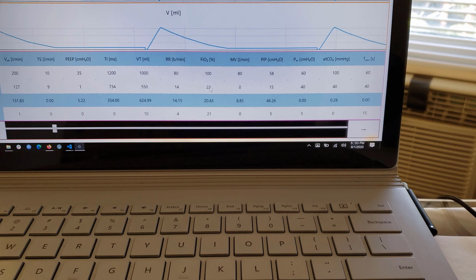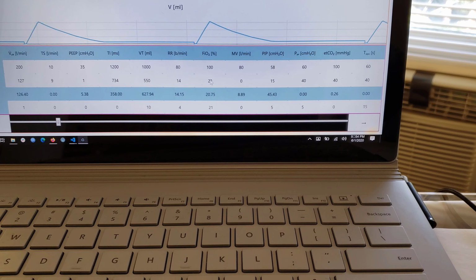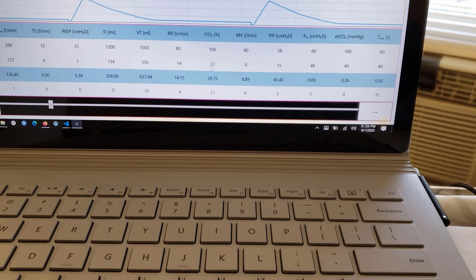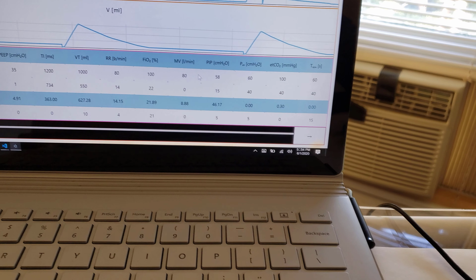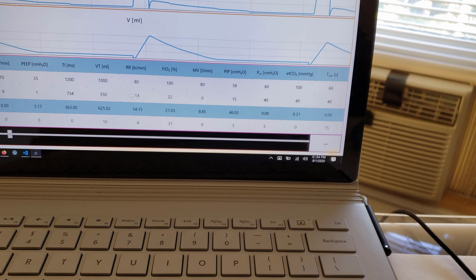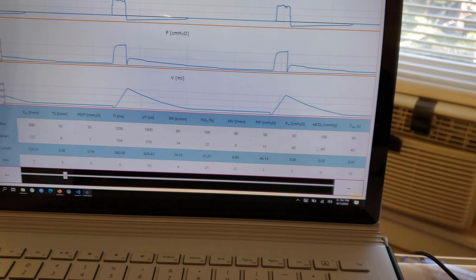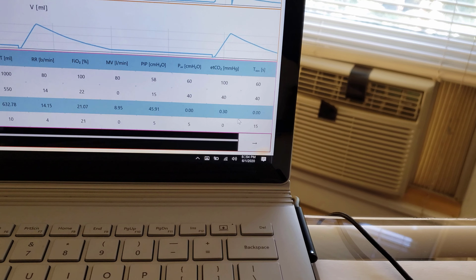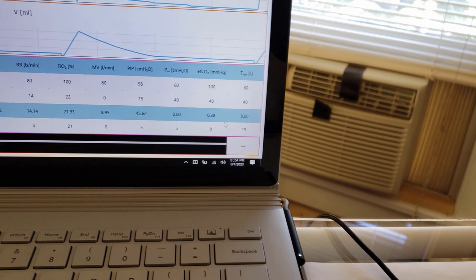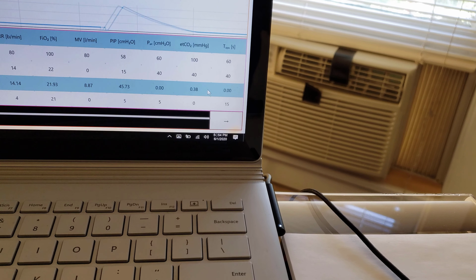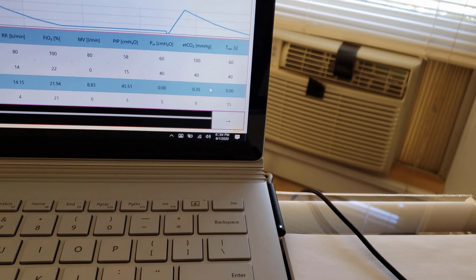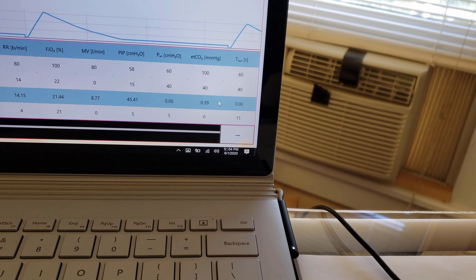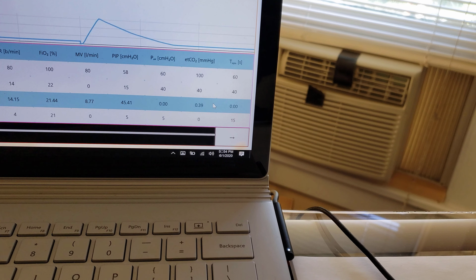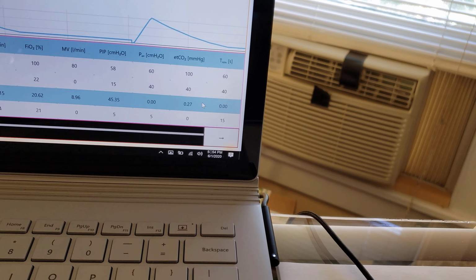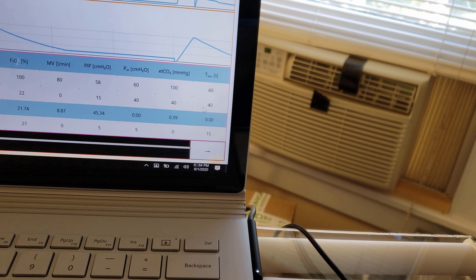There's FiO2. We don't have compressed O2 here, unfortunately, so it's just measuring the fraction of oxygen inside the compressed air tank. MV is just calculated based on a couple other parameters. PIP, that's just the peak pressure from the plot up there. Here is P average. We're not calculating that right now. Here's CO2. Unfortunately, the lung simulator lacks the mitochondria necessary to produce any more CO2 than what goes in, so we're just sensing exactly that. Apnea time has to do with assist control mode, so right now we just have it set to 0.